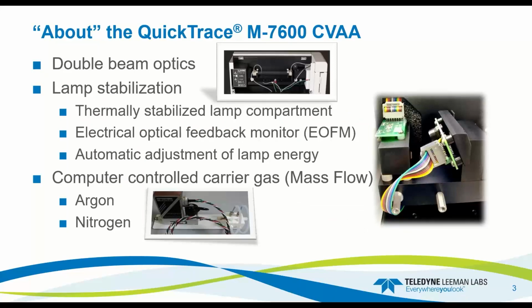The system is double beam optics. We have a lamp stabilization. So there's a compartment where the lamp is and it's heated. It's thermally stabilized. We have a system in there called EOFM, which stands for Electrical Optical Feedback Monitor. So this automatically adjusts the lamp energy as the lamp ages. This process will allow you to keep your method detection limit, your instrument detection limit, your lower limit of quantitation at a steady state as the lamp ages. So it keeps the same energy onto the detector at all times.